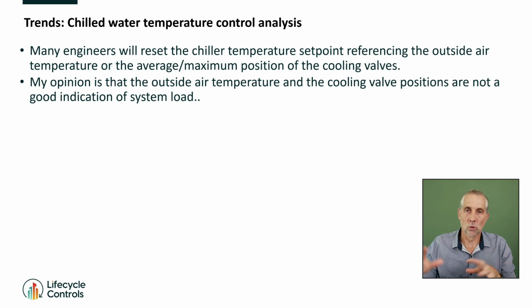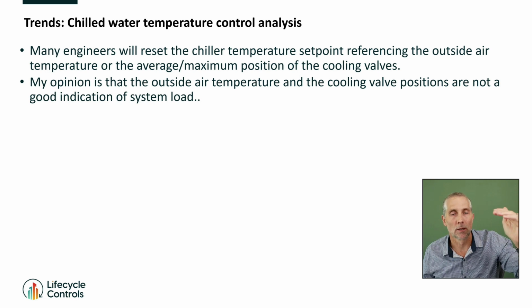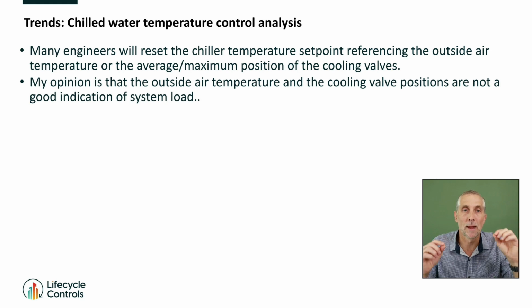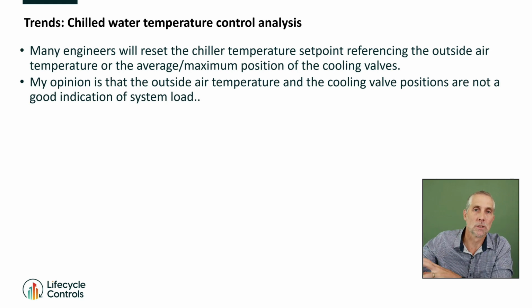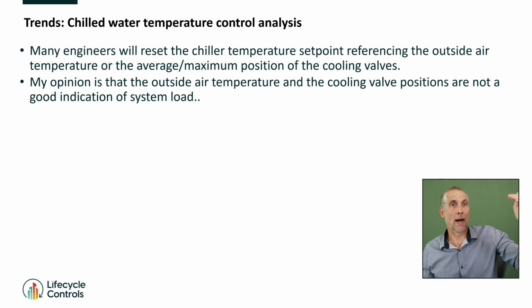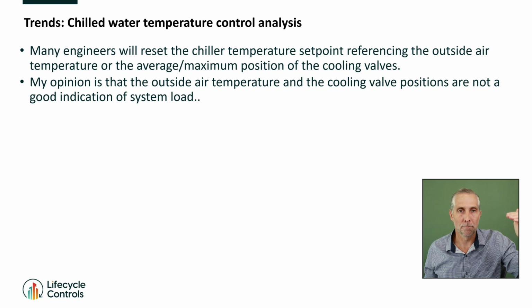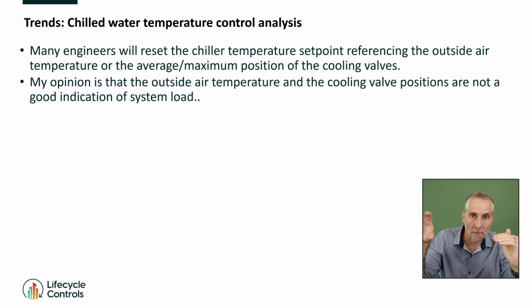So for a lot of you, you know that, that's fine. If you don't know that, you might need to think about it a bit more. But what it meant was that when we started changing the system pressure set point, the cooling valve positions were no longer an indication of the load. So on a hot day, the pressure set point could be up at 250 kPa and the valves are sitting over here. And then on a cooler day, the pressure set point is 150 kPa. The valve is still sitting here.